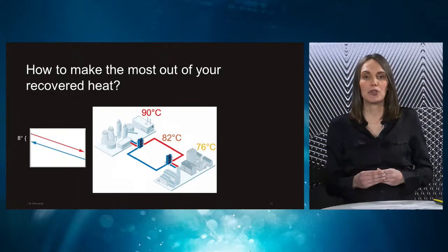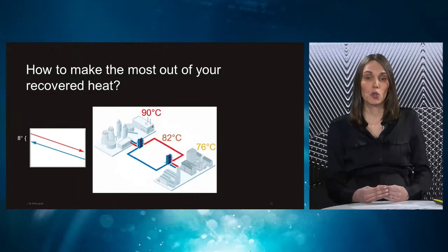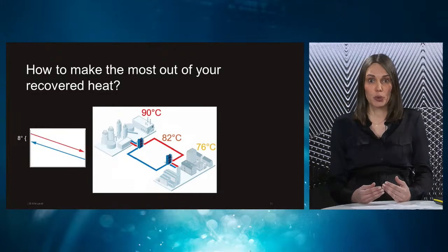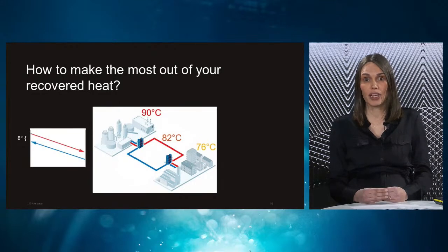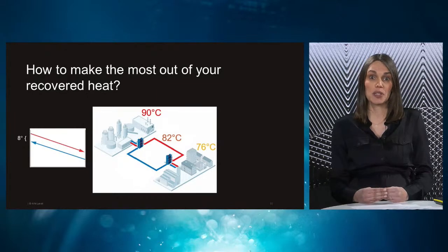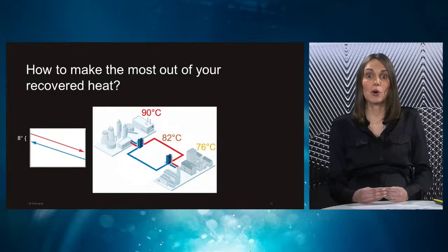This principle with the close temperature approach and the benefits it brings is also true in other cooling and heating applications where we can, for example, have the opportunity to switch to a lower grade utility. If we have a cooling duty where we today need to use chilled water, so very cold water, it could be possible to switch to a cooling water, for example, or in a reboiler, it could be possible to switch to a steam of a lower pressure. And both these situations mean switching to a less energy intensive utility and also most likely a cheaper one. It's also beneficial if we have preheating in interchangers. If we have a close temperature approach, we maximize both preheating and cooling.